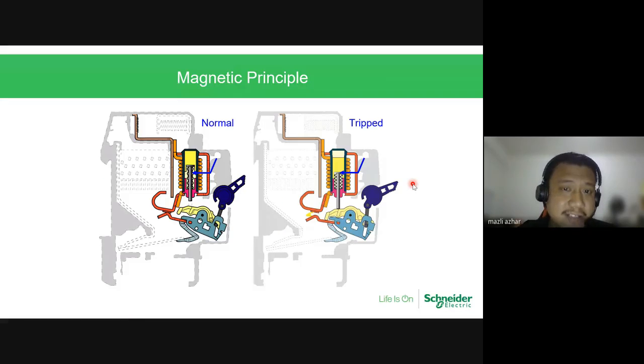So how it looks in a normal condition, you can see the plunger or the solenoid here doesn't have any issue, but when the current increases, the magnetic field increases, then it will push the plunger to open the circuit. And then what happens? The power contact will open, and then the arc created will be extinguished at this arc chute or arc chamber.